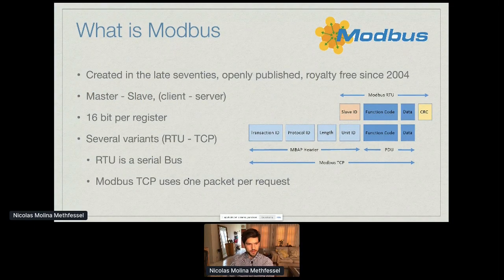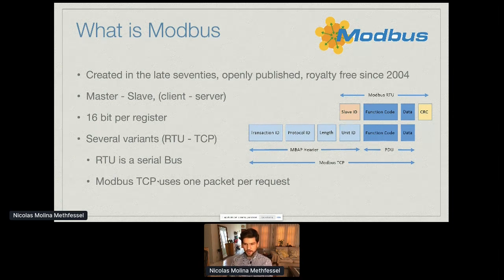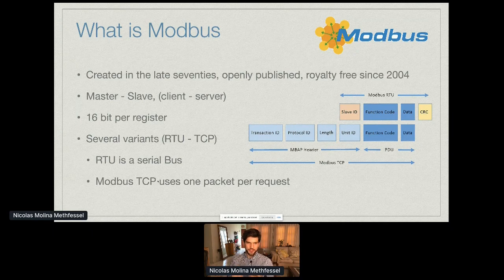I'll explain a little about Modbus. It's a protocol created in the late 1970s, openly published and royalty-free. It was created by Schneider Electric and is now an open standard. Because it was created so long ago, it still has a very old mechanism: it is a master-slave, client-server system where one device has to continually ask for updates from the device that has the information. The device holding the information cannot push updates — it has to wait until it is asked. All information is stored in 16-bit registers. It's a really old system.